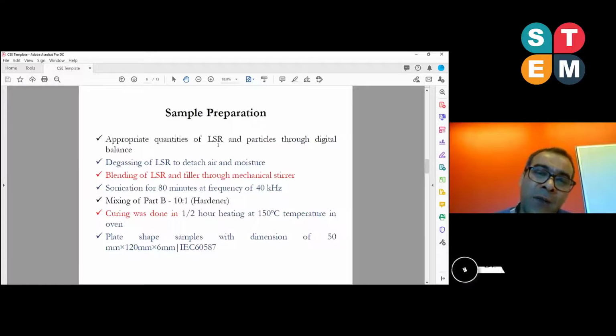We have to add our additives in the polymer, but we have to be careful. The degassing step should be taken very carefully, because we don't want any moisture or air trapped in the insulation sample, because if air is trapped in the insulation, that can start electrical discharges in it. So we use the mechanical mixer, and after that we use sonication. That is water bath sonication.